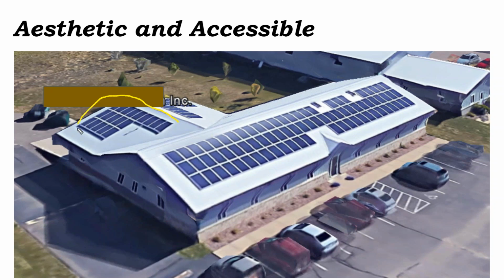But when it comes to sections of an array, like this section, 1, 2, 3... up to 19 modules, it turns out that with this microinverter you could fit up to 19 on a circuit, since they had a lower amperage than the latest model. So when we said we're going to fill up our south side but also have a subarray facing east and one facing west, we intentionally designed that circuit so it only has one circuit in that section, not two.